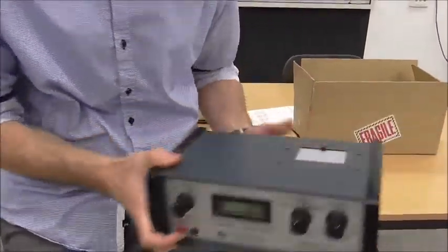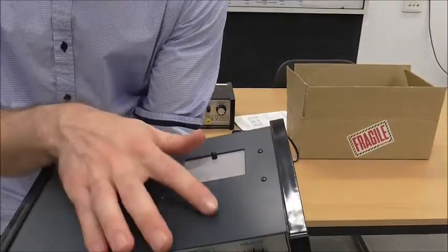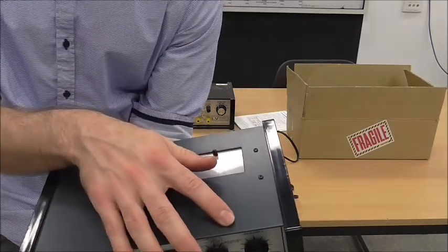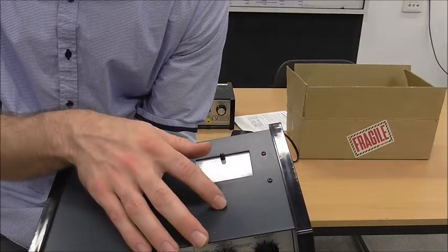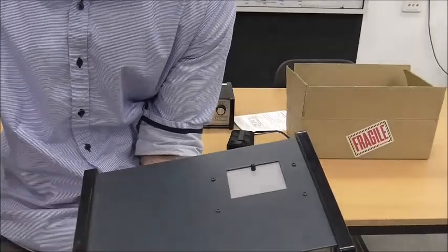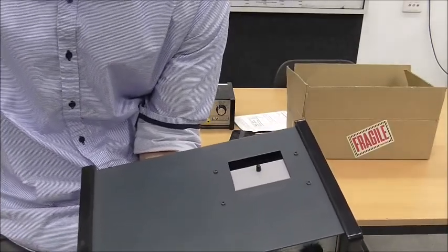So it's actually a fairly simple apparatus. The light comes in the back, passes through a filter, then there's the phototube here. The light then hits the cathode material. If it has enough energy, it can emit electrons. They then flow across to the anode, and then there's just a completed circuit here, and within that circuit there's a nanoammeter which measures the amount of photocurrent.